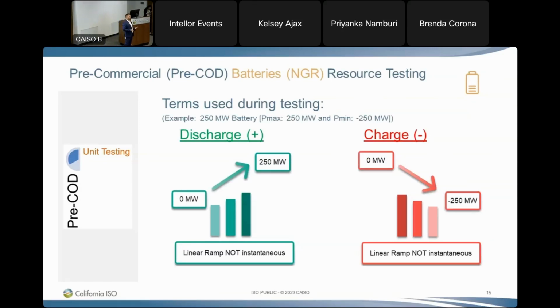So discharge is, in this case, I gave you an example of a 250 megawatt battery. Pmax is 250 megawatts, Pmin is negative 250. So you got a discharge from 0 to 250. That's what we consider a discharge. So when you're putting megawatts out on the system and you're not load, that's a discharge. A charge is 0 to negative 250, anything in that range we refer to as a charge. And notice on both of those, I stated a linear ramp, not instantaneous.